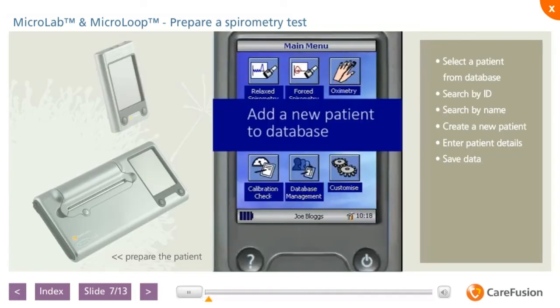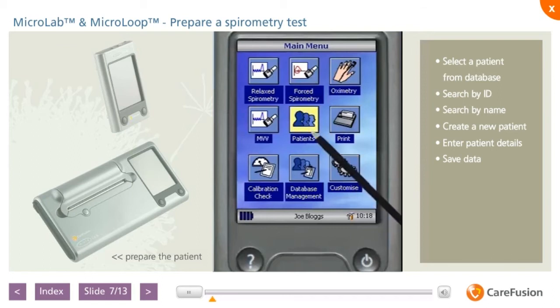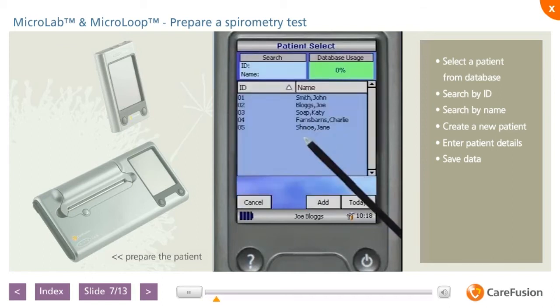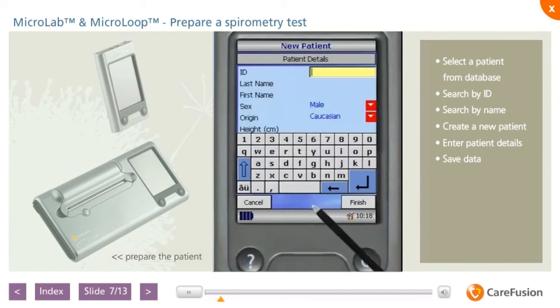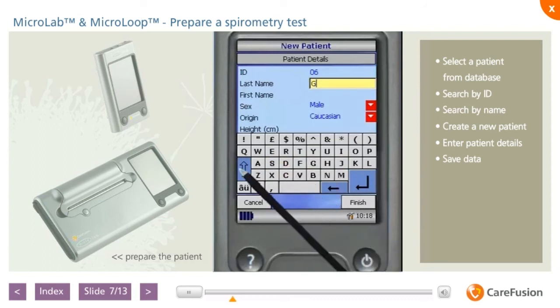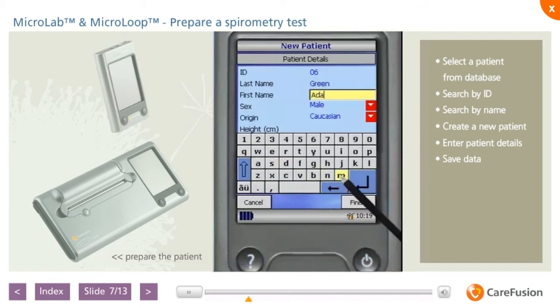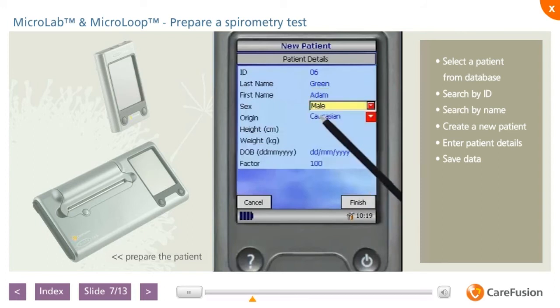Prior to performing a test, we recommend that the patient's details are entered into the spirometer for storage in the database. Use the stylus and on-screen keyboard to do this. It's important to ensure that the correct name, ID, and demographic details are entered for the patient being tested. These details will also be used to calculate the applicable reference values. When you've done this, select Finish.